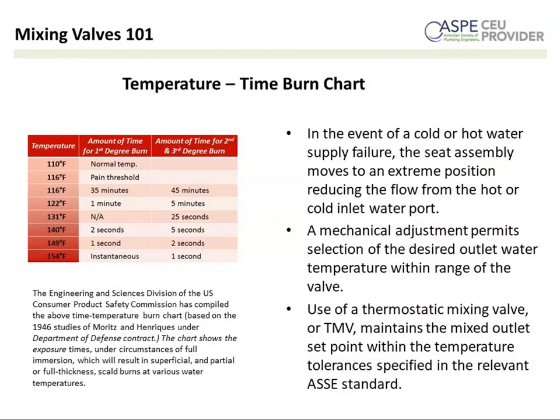This is, again, talking a little bit about the temperature and the burn chart. So this gives you a little bit more specific information. This is, I believe, from the Engineering and Science Division of the U.S. Consumer Product Safety Commission. In this particular diagram, we talked before that burns can occur at 120. This one actually at 116. It takes a while, but you can incur a third-degree burn in 45 minutes. So, let's say 116 to 120. At 122, it's 1 minute and 5 minutes. And again, when you get into temperatures above 150 degrees, it becomes virtually instantaneous. What mixing valves do is their goal is to prevent these kind of temperature increases based on various conditions.